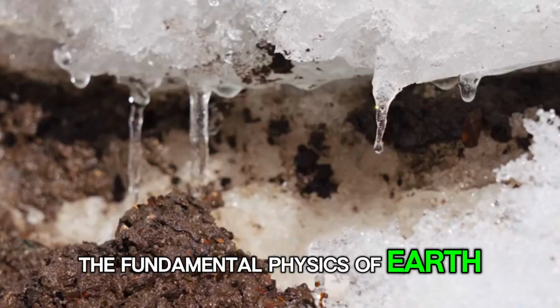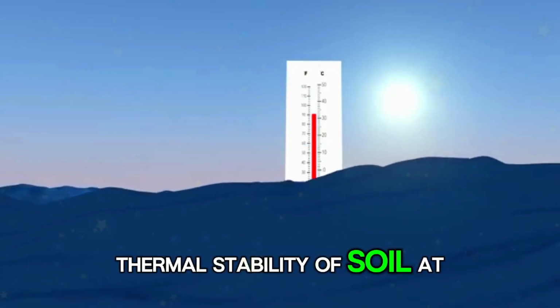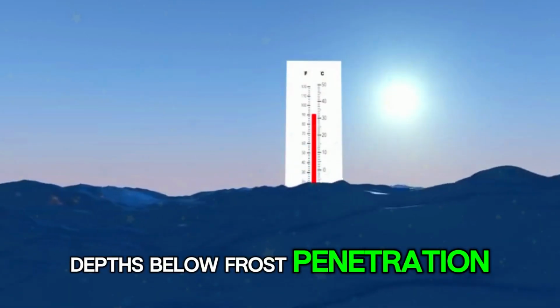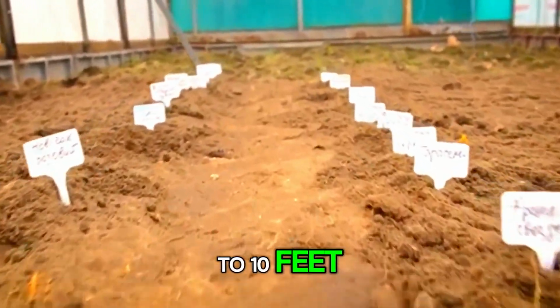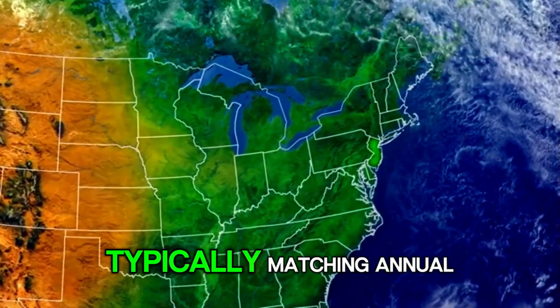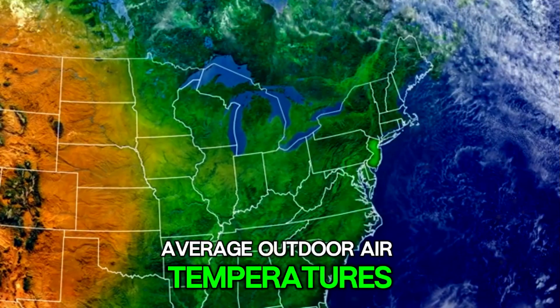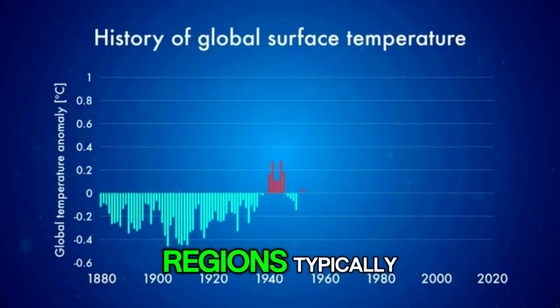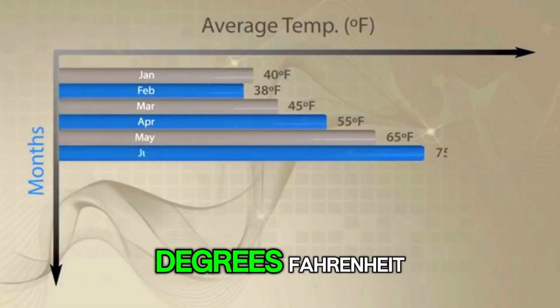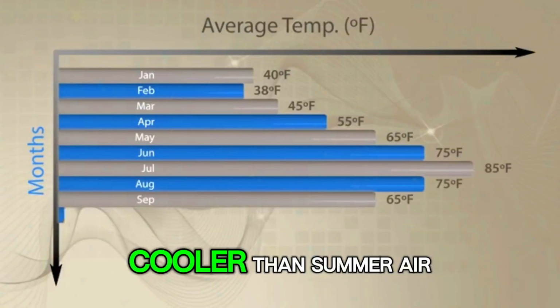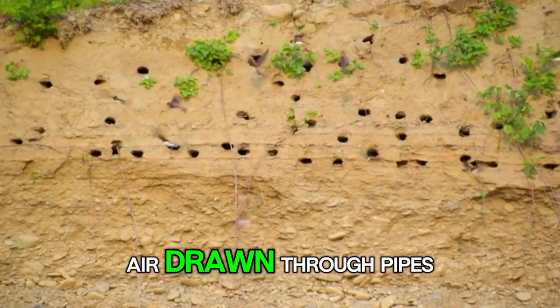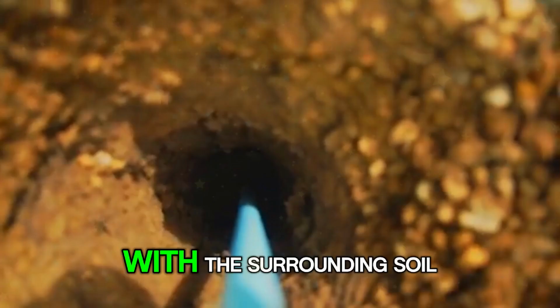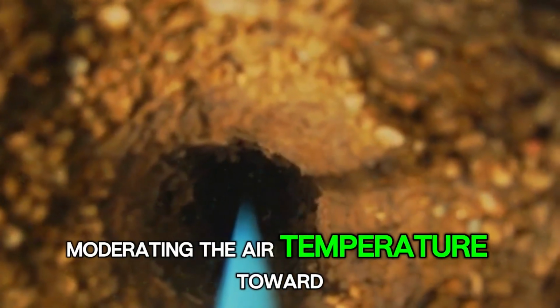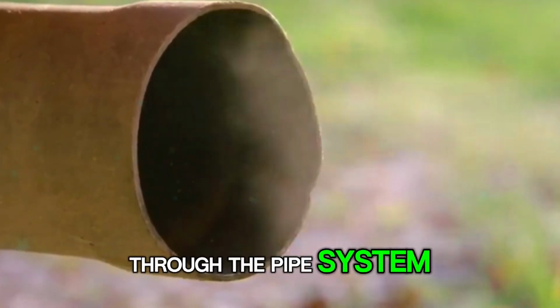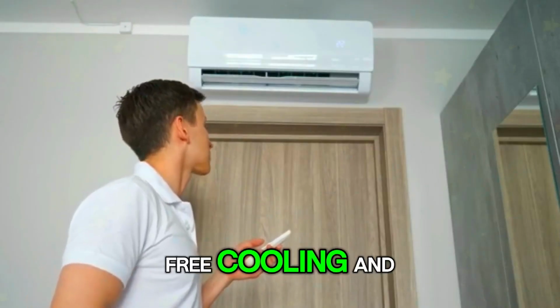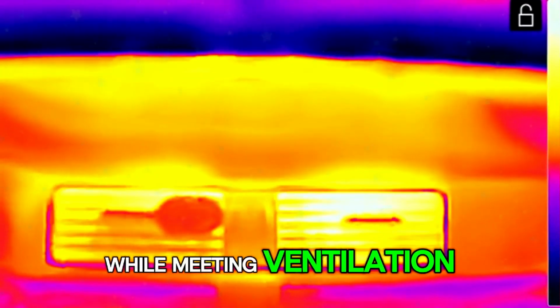The fundamental physics of earth tube performance exploits the thermal stability of soil at depths below frost penetration. Soil temperatures at depths of 6 to 10 feet remain remarkably stable throughout the year, typically matching annual average outdoor air temperatures for the specific location. Temperatures in temperate regions typically stabilize at 50 to 60 degrees Fahrenheit, warmer than winter air and cooler than summer air. Outdoor ventilation air drawn through pipes buried at these depths exchanges heat with the surrounding soil, moderating the air temperature towards soil temperature as it travels through the pipe system. The resulting conditioned air provides free cooling and heating relative to outdoor conditions while meeting ventilation requirements.